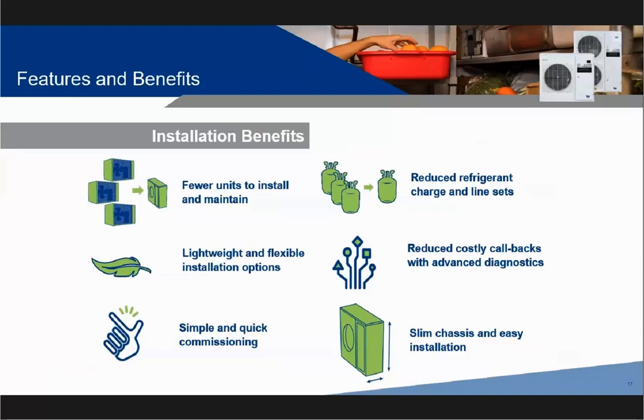And then simple and quick commissioning. To get the unit up and running, there's only 3 set points: refrigerant, time clock, and suction pressure. And something I didn't mention is this is also a benefit from the fixed side as well. Our fixed speed X-Line also only has 3 set points, refrigerant and time clock, same as the digital. But instead of suction pressure, the fixed speed has a cut in and cut out. So both are very simple, with very quick commissioning, and easy to get up and running.